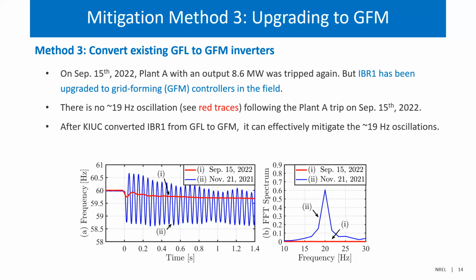And this result is showing actually last year on September 15th, a similar event happened again, but with a smaller amount of output from the KPS. As you can see here, after we converted the IBR1 into the grid forming mode, this definitely can smooth the entire event.